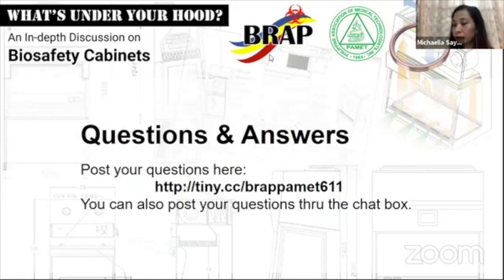And I think we discourage bigger biosafety cabinets that are class 2 in size, mainly because if you have more people working across an open sash, you have more disruption of the air curtain. Now, for class 3 biosafety cabinets, yes, 2 persons can use a class 3 biosafety cabinet as long as you have enough gloves in place. For crowding purposes, we tend to use it sparingly. The most is 2 persons, not 3, not 4.